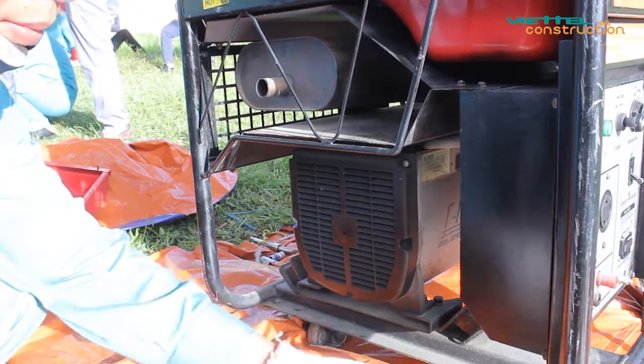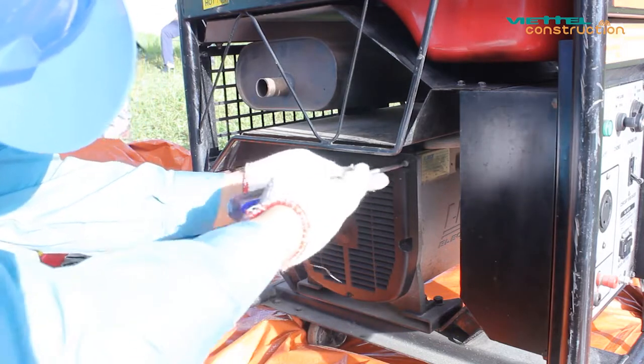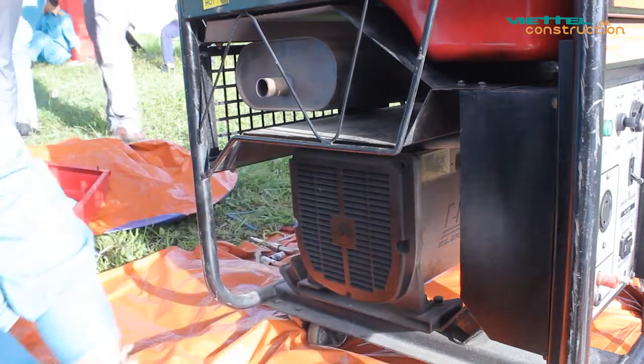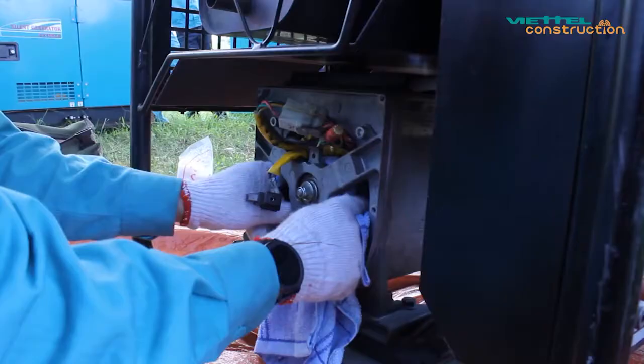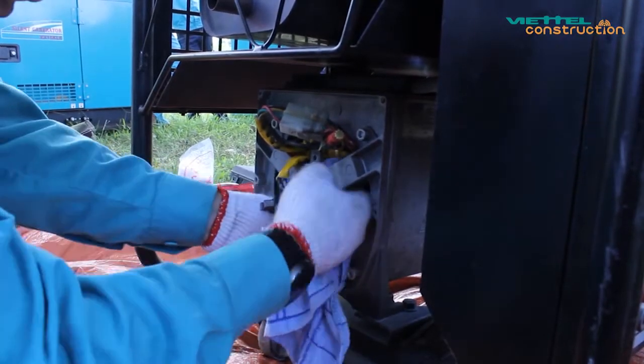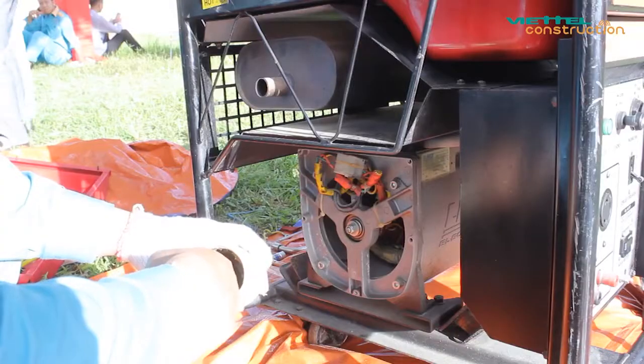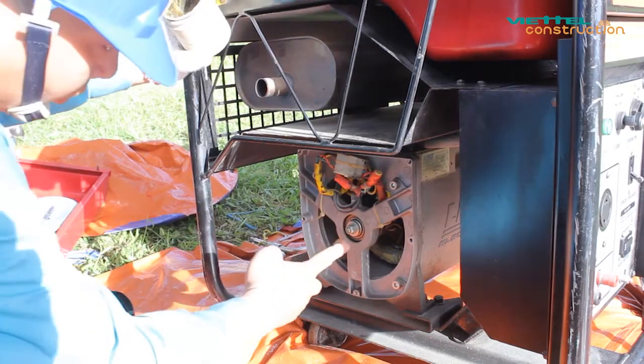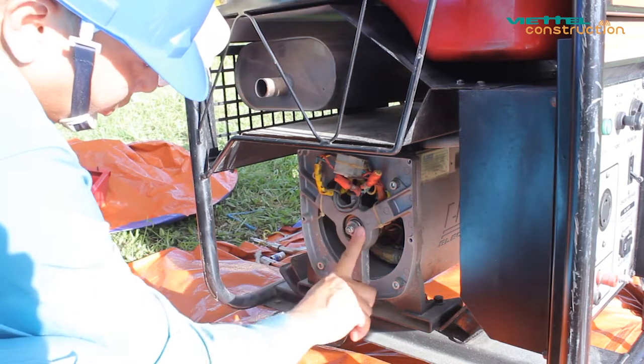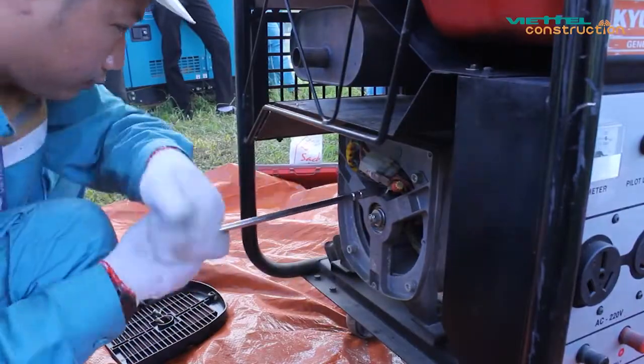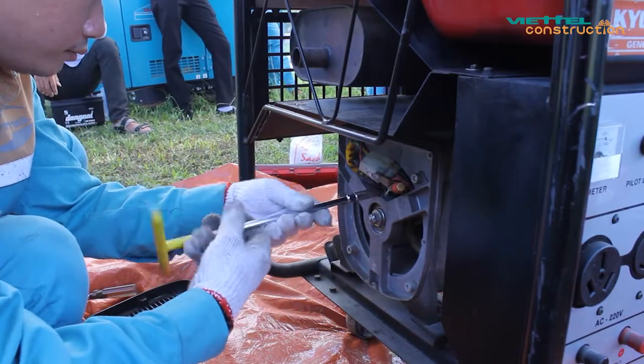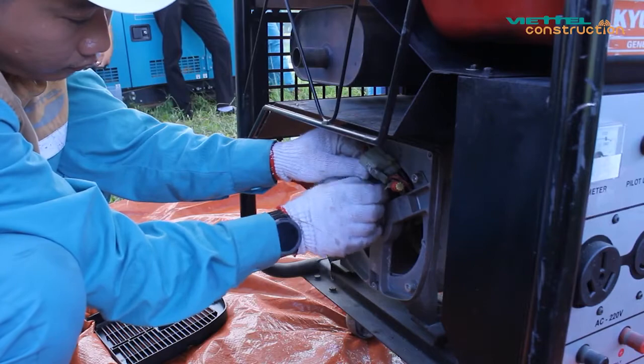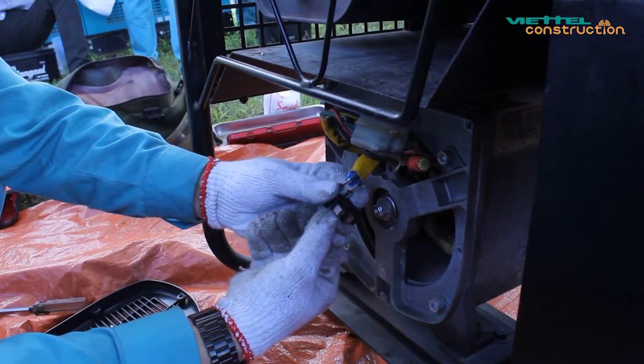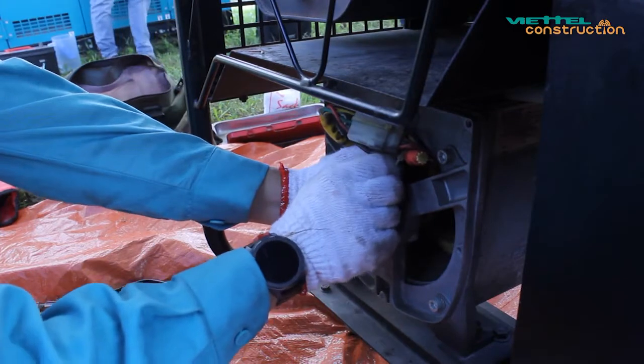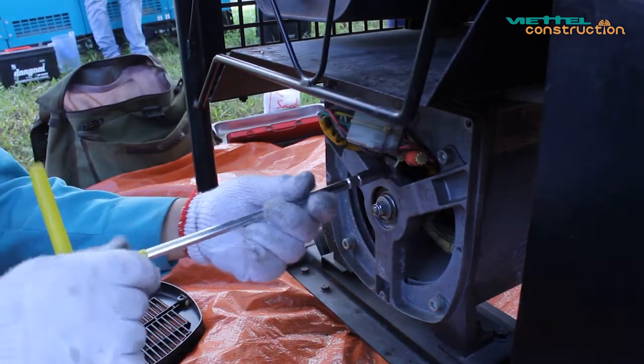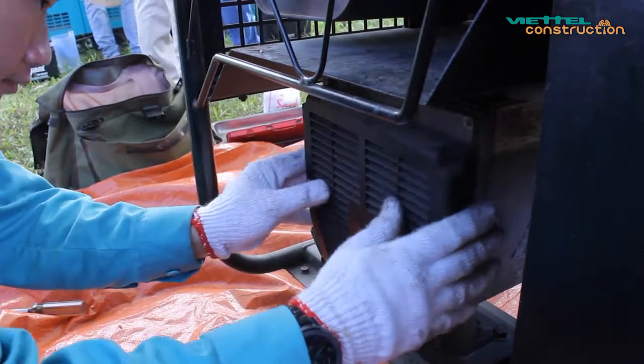Use a screwdriver to remove the protective cap of the alternator. Cleaning the stator winding and using industrial grease into ball bearings. Remove and check the brush of the excitation coil. If the brush is worn out more than 2/3, we proceed to replace the brush. Reassemble the brush. Then reassemble the protective alternator.